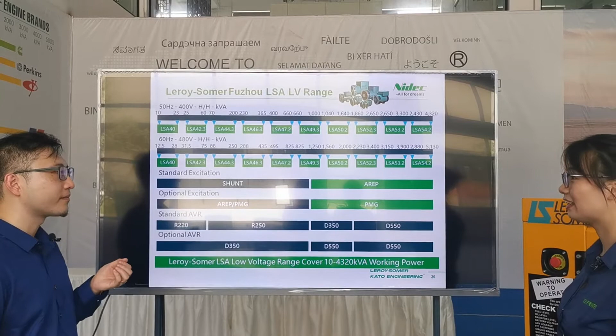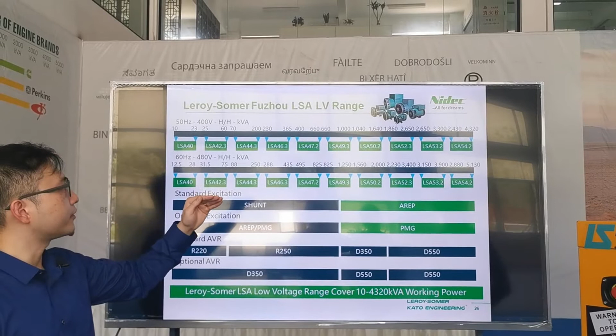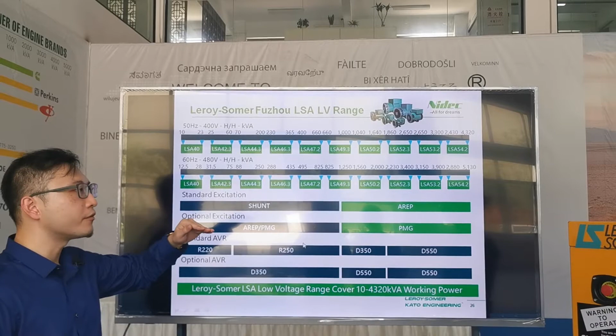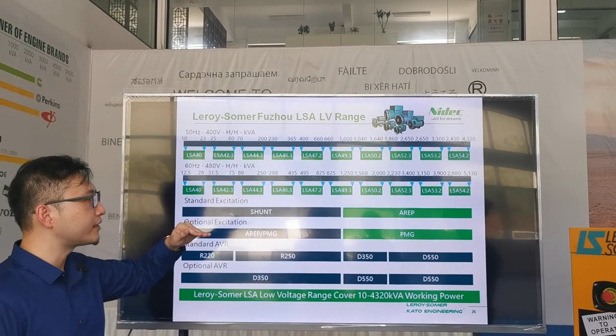One more thing to highlight: at 400 volts voltage level, the highest power of LSA low voltage product is 4,320 kVA. At this highest power and at 400 volt low voltage, the current of this machine will be very high, up to around 6,300 amperes, which is quite dangerous.